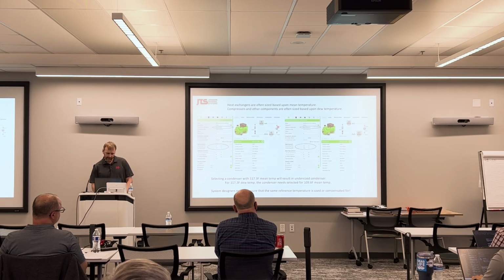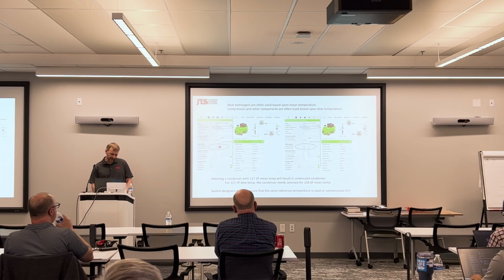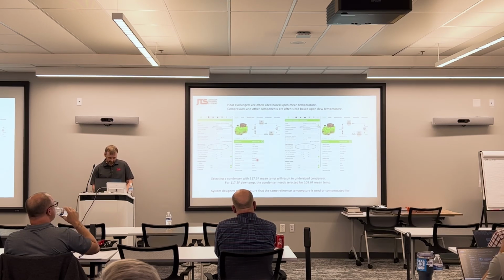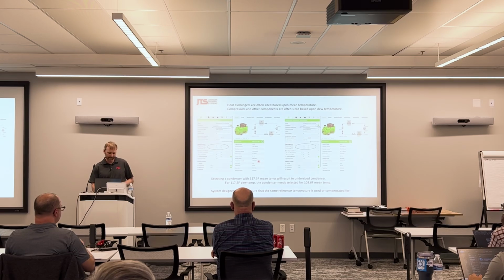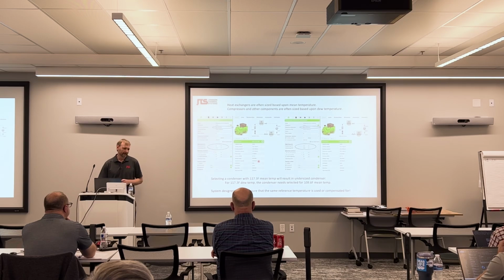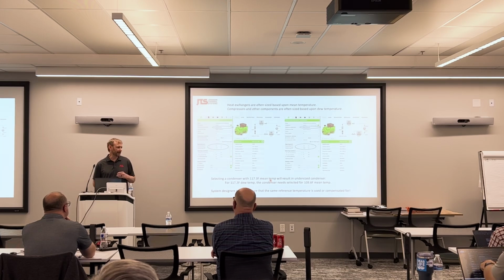So as indicated here, your heat exchangers are often sized based upon a mean temperature difference. Compressors and other components are often sized based upon dew temperature. In this example, I've got a couple of Bitzer compressors pulled up. The first example is R455A. We're referencing dew point: the 30-degree saturated suction temperature and 117.3 dew point condensing temp. So it's telling us that we need a condenser capacity of 200,000 BTUs per hour. If we went to our condenser supplier and said, we need a condenser that does 200,000 BTUs per hour at 117.3 degree condensing temp, you have to be very aware of how that condenser coil supplier rates their condensers. If they come back to you with a selection and say, here's your 117 degree condensing temp, oh, by the way, we rated this at midpoint, all of a sudden your condenser is not properly sized.